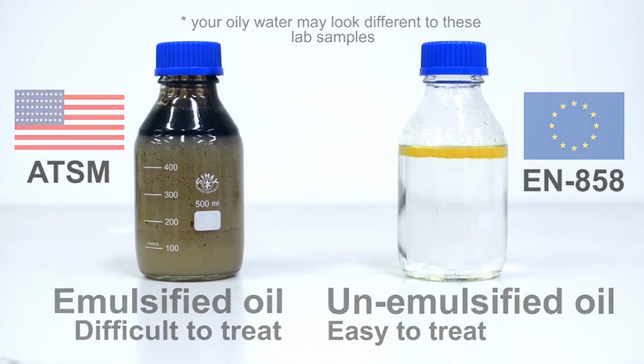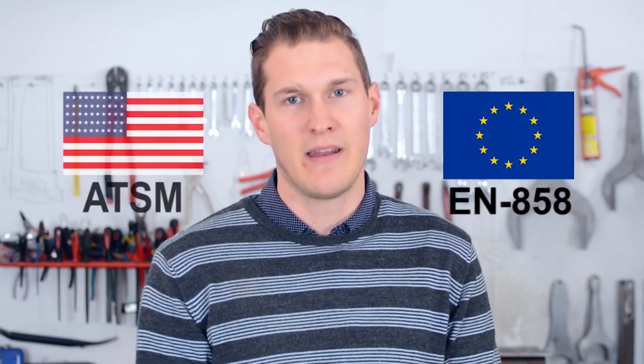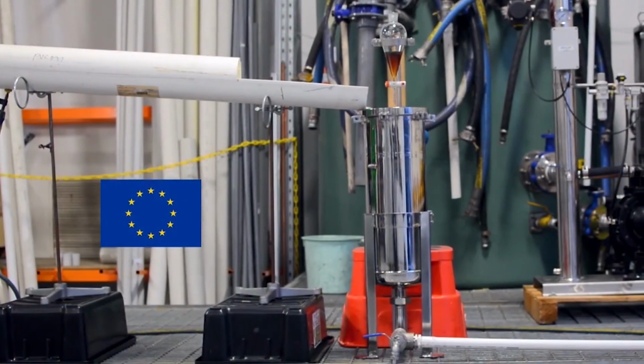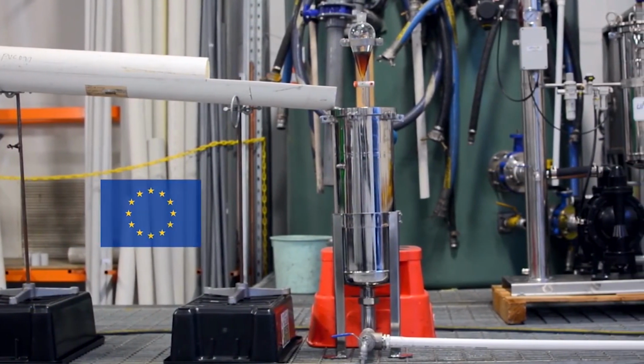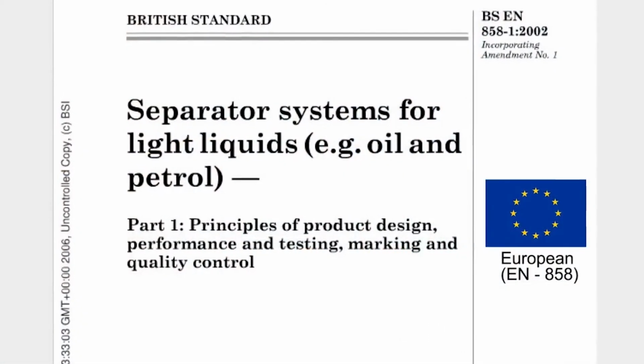Here is Ivano, our engineering manager, to look at two typical standards, the European and the American, and examine how they work. There are many different standards to test for the performance of oil water separators. Each one of them has a variety of applications. They can range from the very simple, where you're testing for simple oil spills, to the more complex, where you're testing for emulsified oil. One of the standards used by oil water separator vendors to test performance of their equipment is EN 858. As you can see, we've simulated that test here, and it's a fairly simple test.